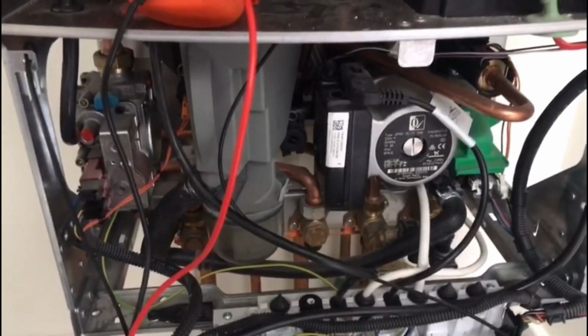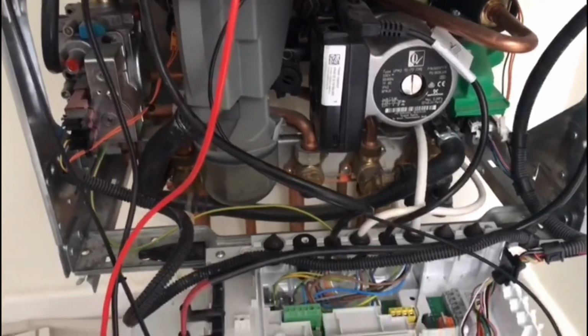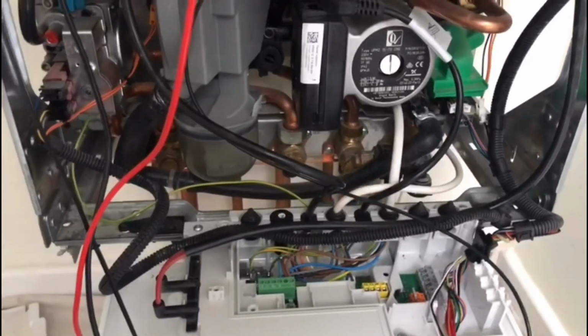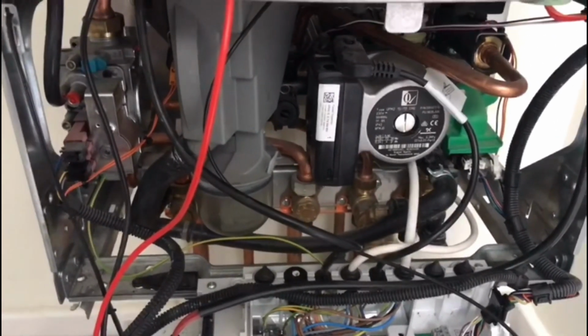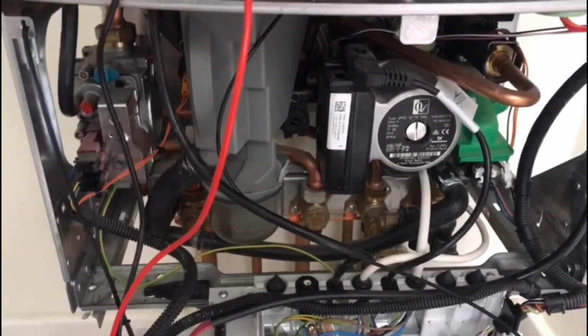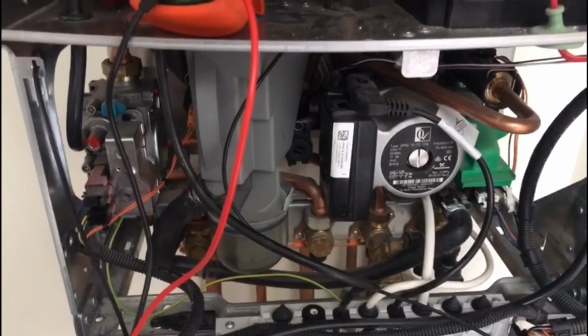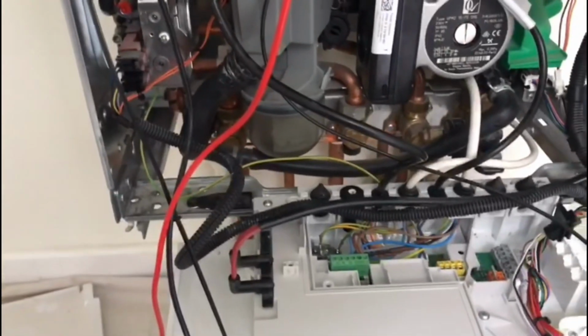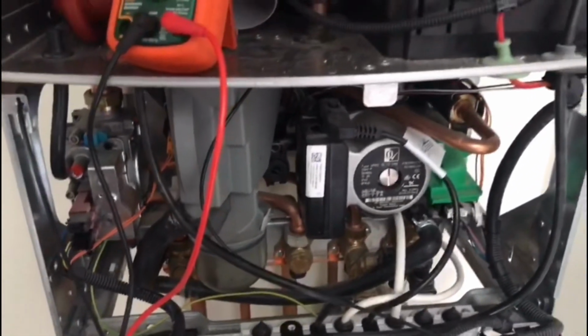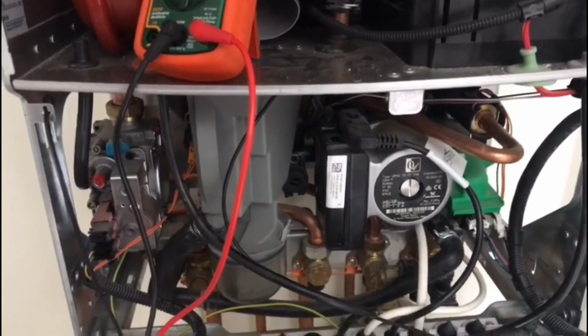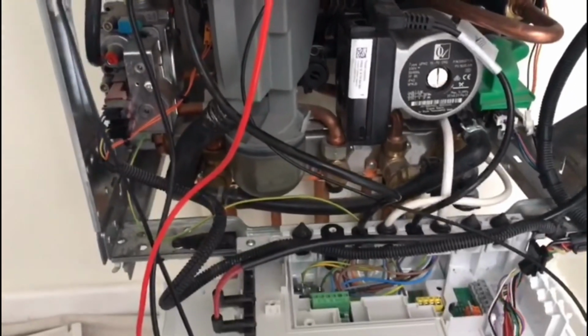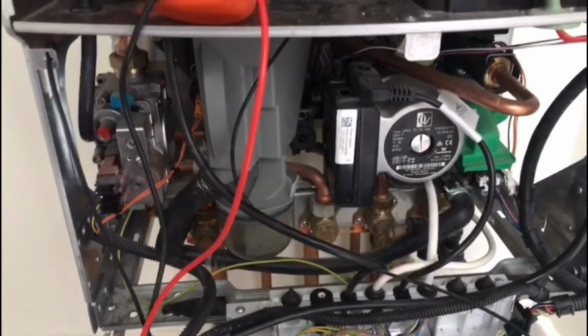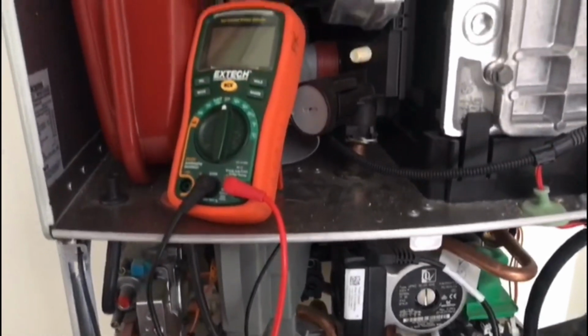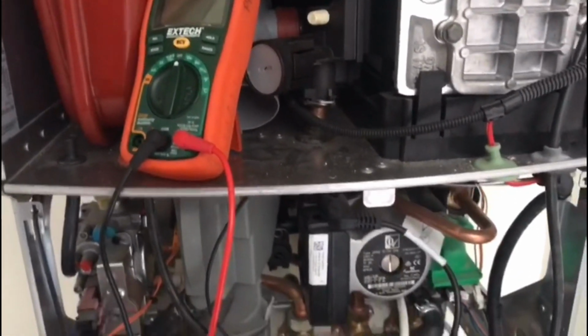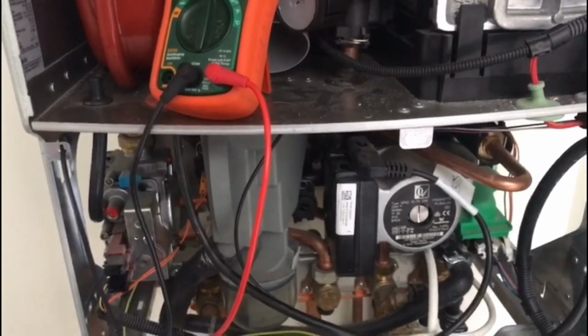Also, certain boilers will not rectify properly without the neutral being connected properly. On a Baxi 105 for instance, you're wondering why a Baxi 105 will fire but won't stay lit. Do a quick electrical check, could be your neutral's the wrong way round. It's quite a simple check, but that's the electrical checks concluded and tells you that everything is fine and in safe working order with this boiler. So I'm alright to continue, and I'll show you how to do the service on the CDI.